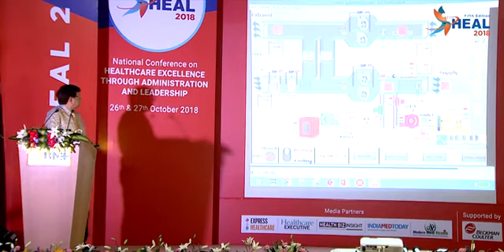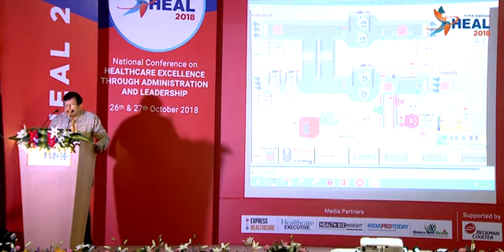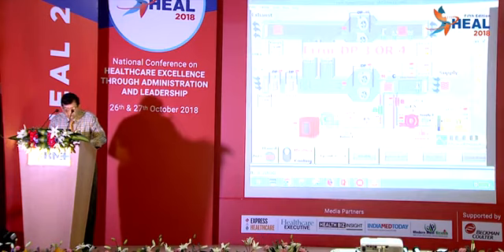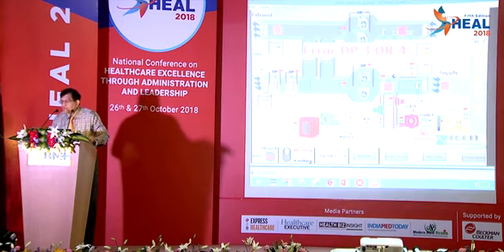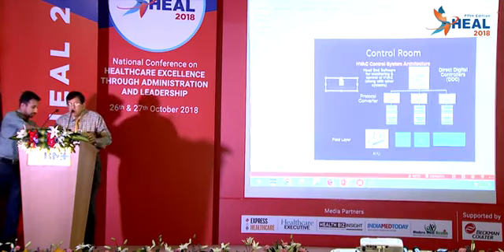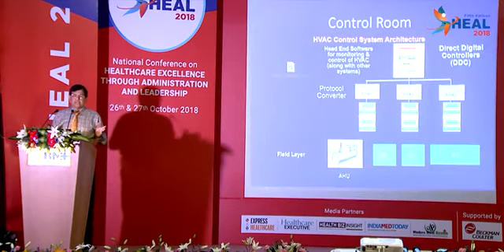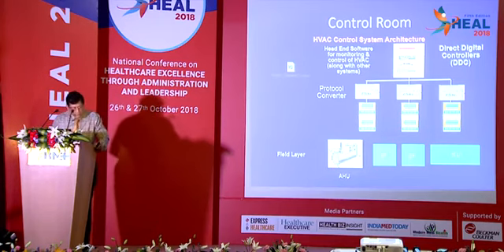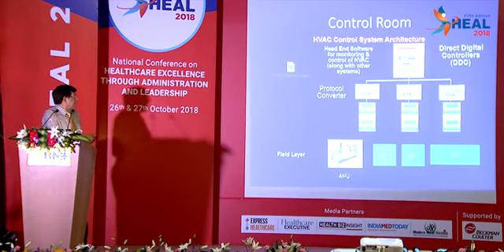Let's discuss some fault cases and error messages. If we have a problem in the differential pressure sensor of filter 1, let's see what we got. We see that we have a signal that shows that filter number 1 is dirty and we need to clean it. Also for filter number 2, it will indicate that it's dirty. And now for the fan, if we have a problem in the differential pressure sensor, let's see what we got. First of all the fan will turn off and an error will show. So what I wanted to tell you is that all this is happening while you are sitting in the control room. You can change the temperature. You can even monitor the filters. That is what has been shown to you. You can increase the fresh air component. This is what you will have in the control room.